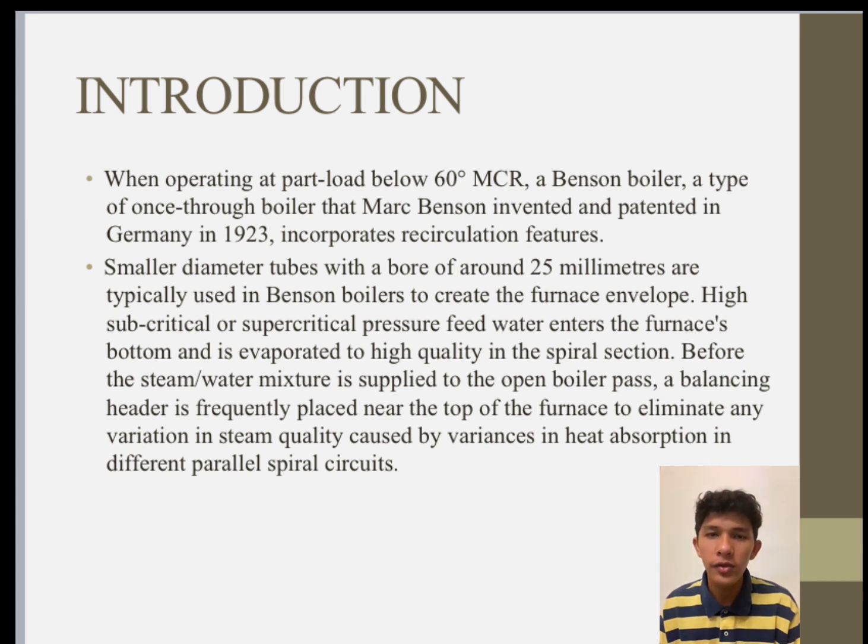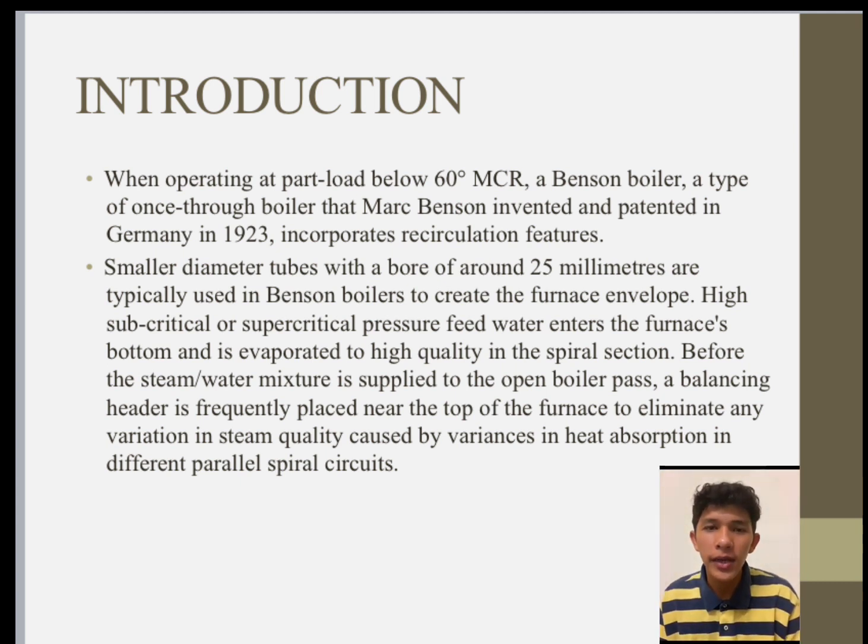recirculation features. Second, smaller diameter tubes with a bore of around 25 mm are typically used in a Benson boiler to create the furnace envelope. High subcritical or supercritical pressure feed water enters the furnace bottom and is evaporated to high quality in the spiral section.